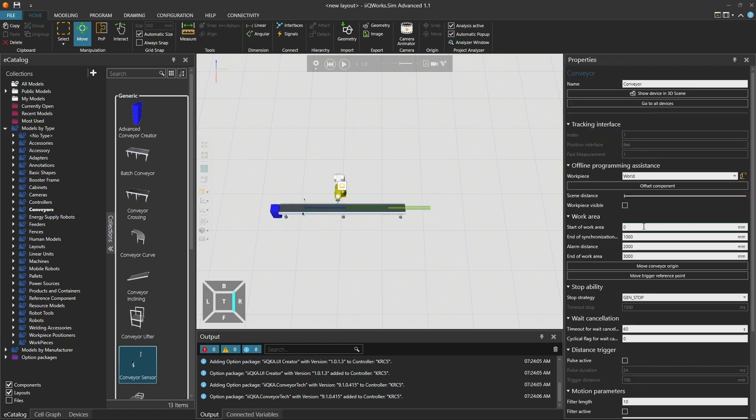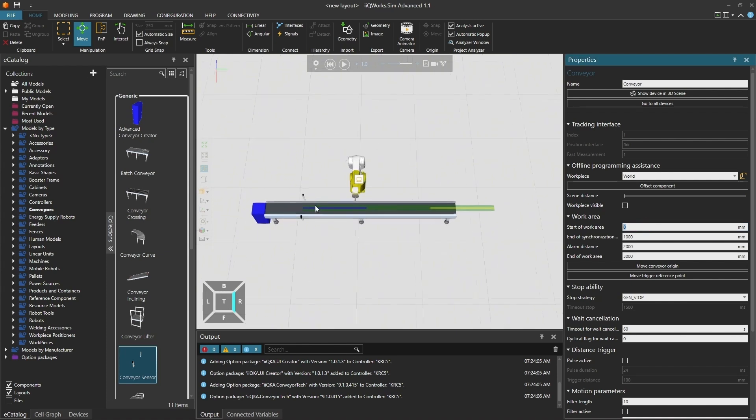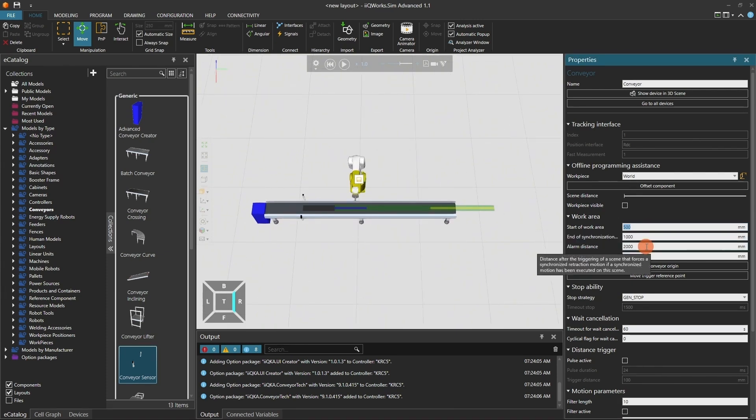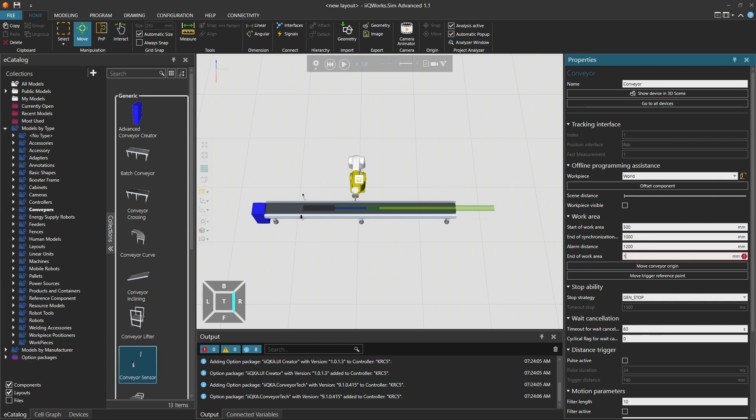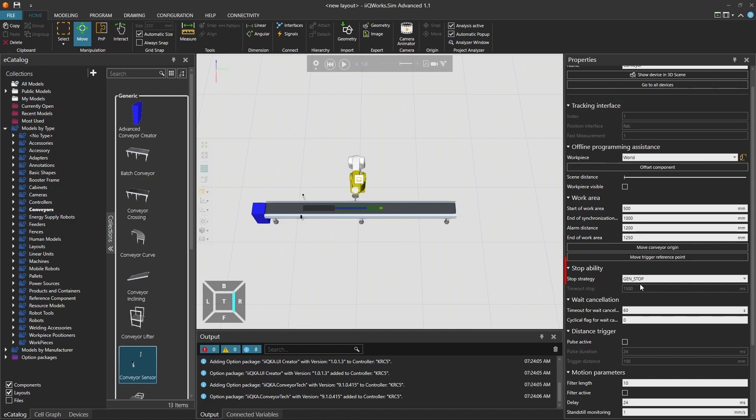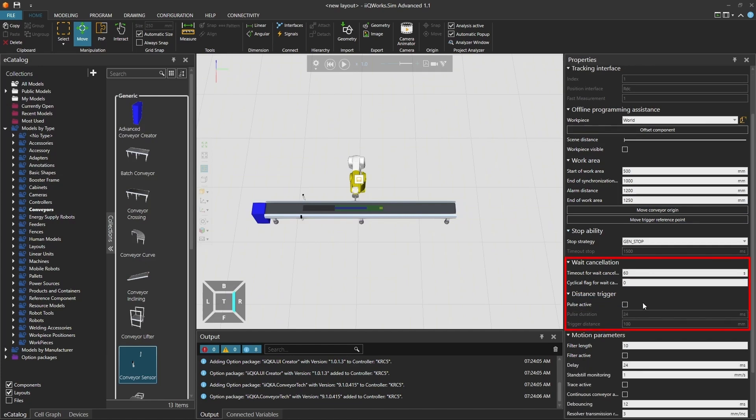Let's now adapt the further configuration of the conveyor behavior. Click on the conveyor and go back to the Conveyor Tech tab. Next, adapt the work area of the conveyor. You can adjust the start and end of the work area, the synchronization area, and the alarm distance depending on your application. You can select the stop strategy that best fits your application. Next, you can adjust the wait cancellation or distance trigger settings. You can also fine-tune the motion parameters to match your process requirements.